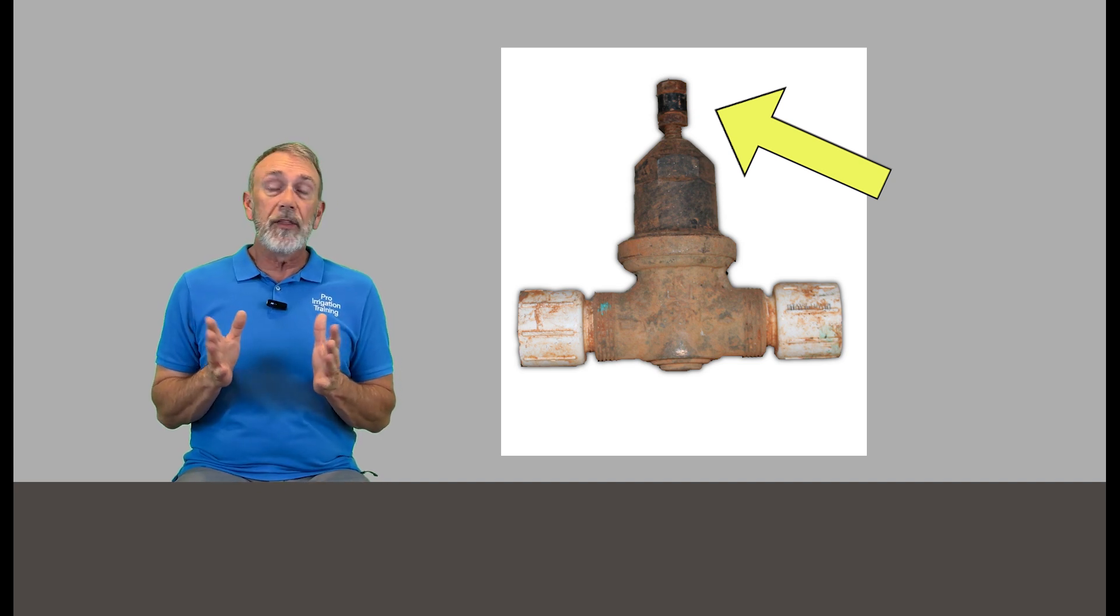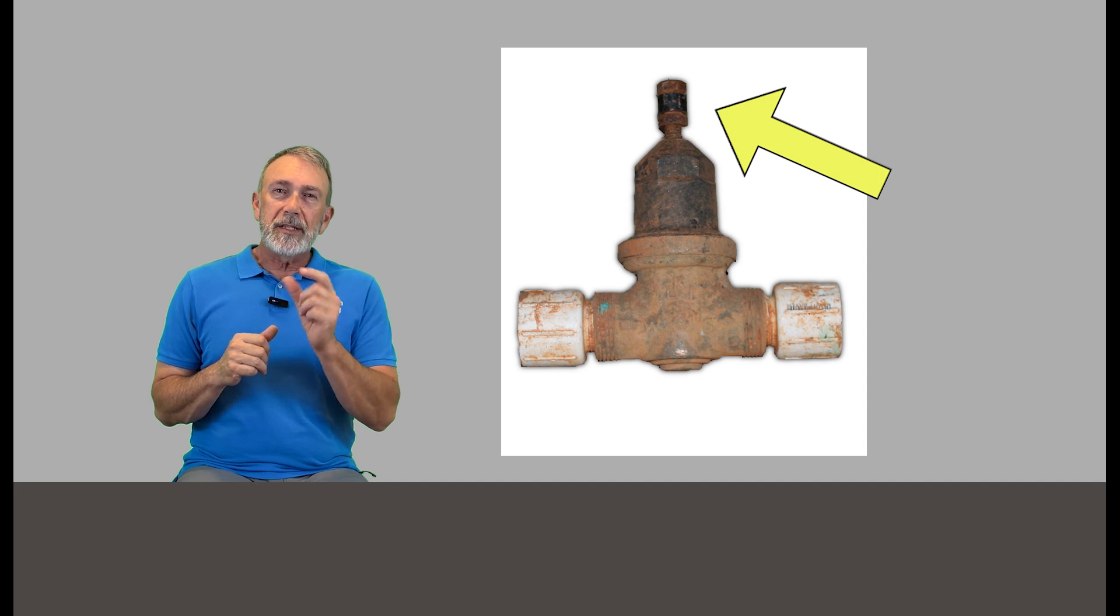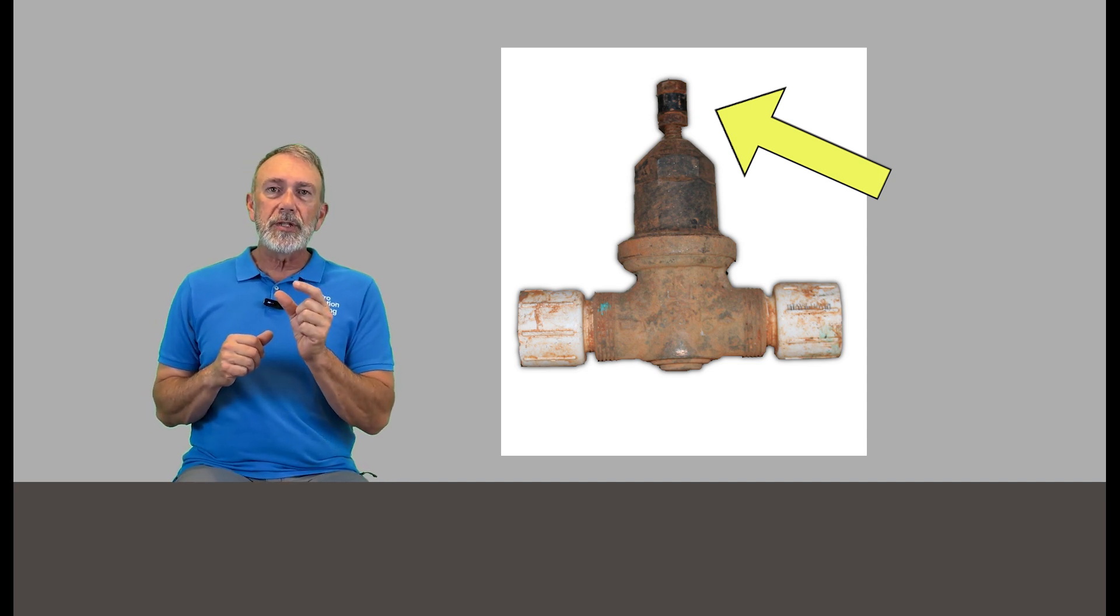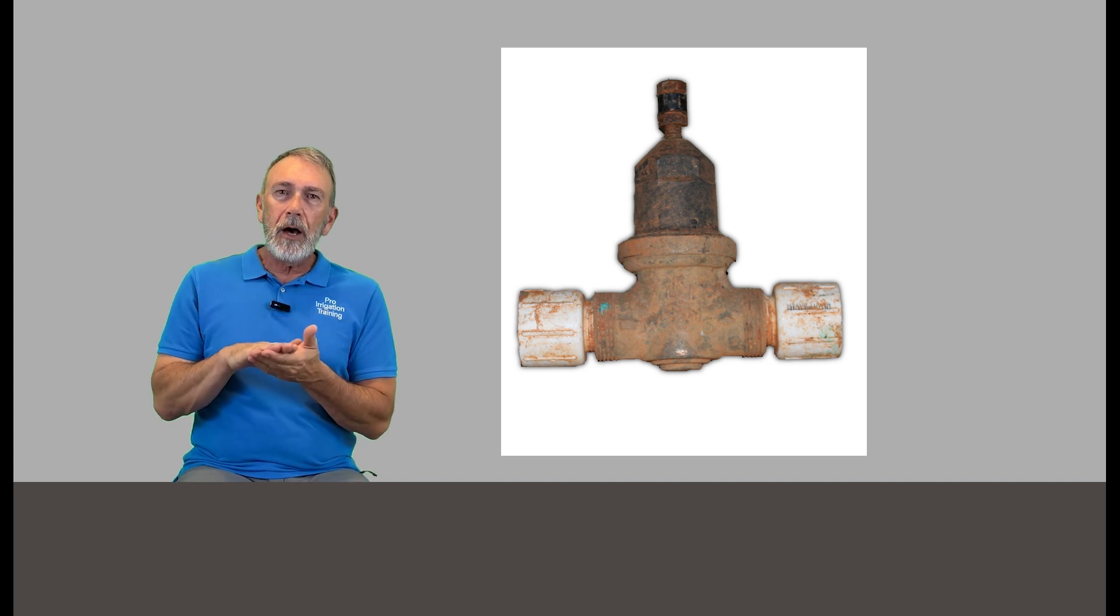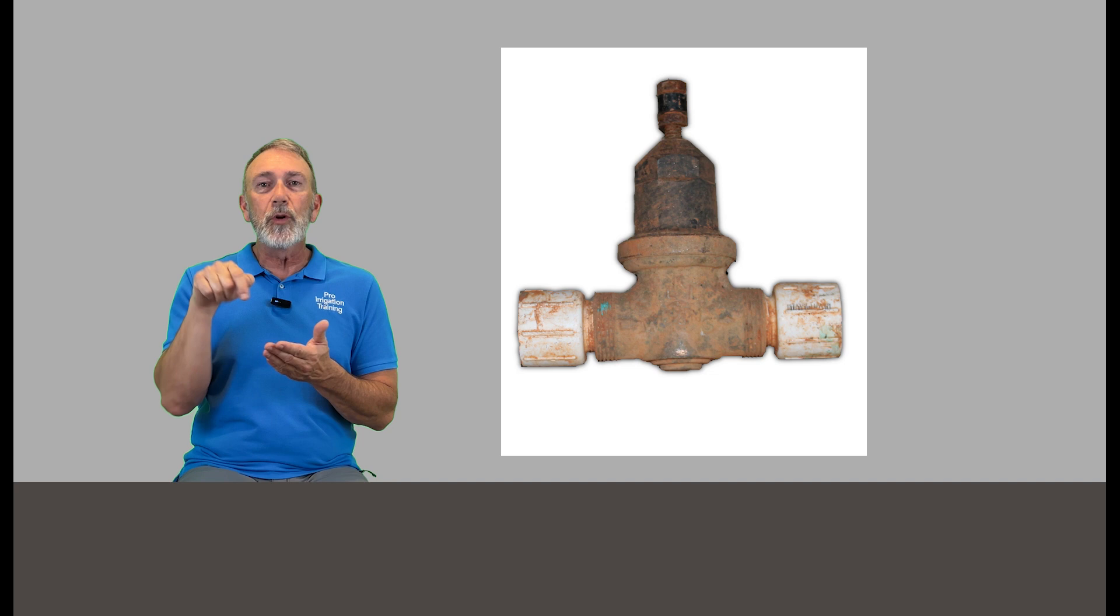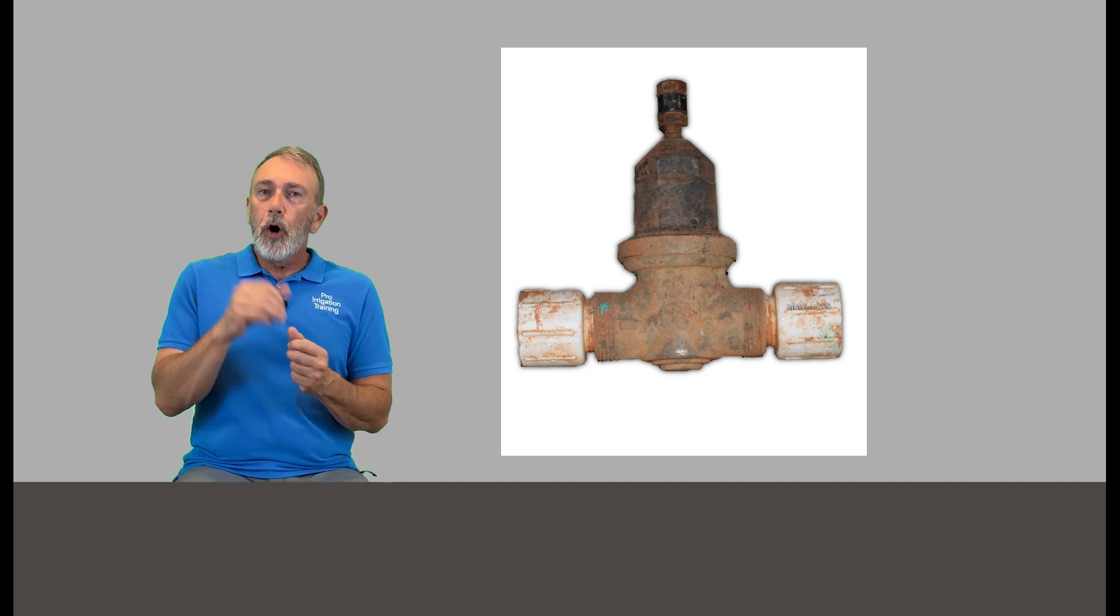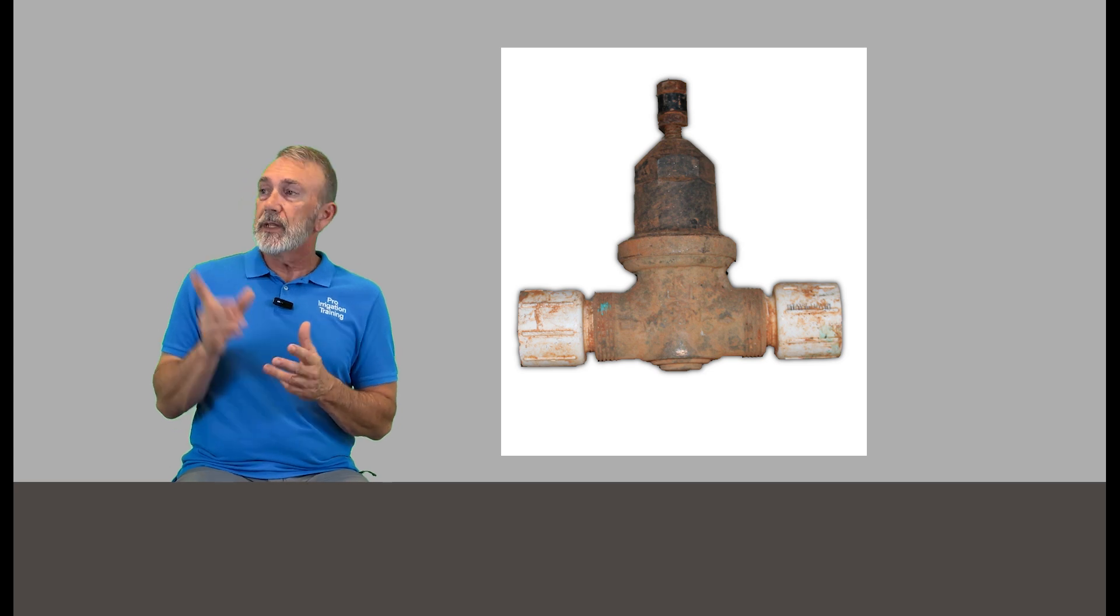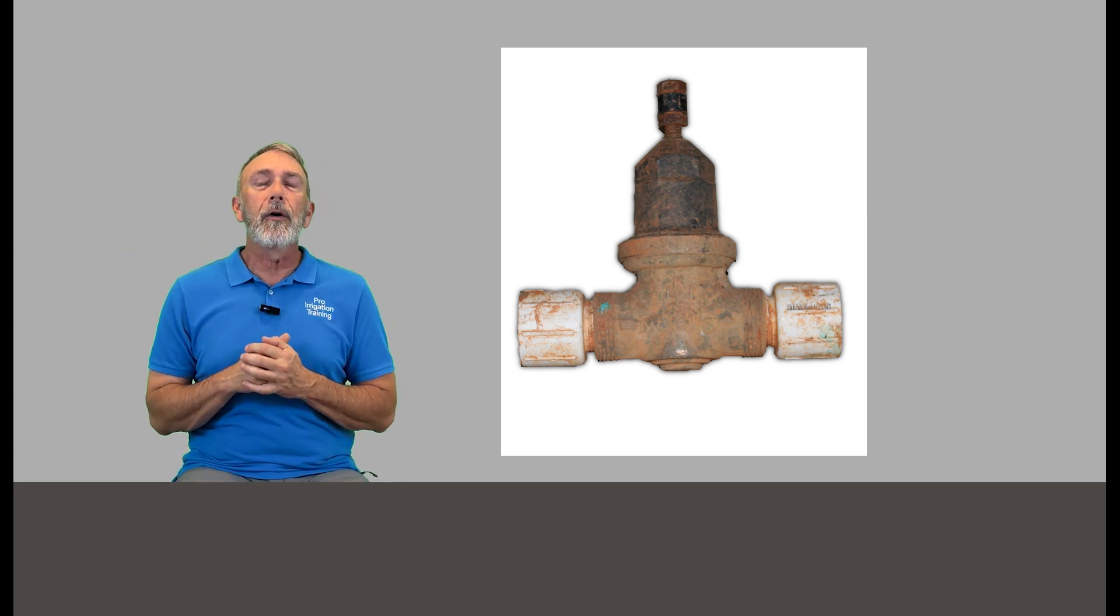On these pressure reducing valves, every one I've ever dealt with, the adjustment of it is kind of backwards. It's not righty-tighty, lefty-loosey. Whereas righty-tighty, you would think that that would shut it down and close down the pressure, but actually a clockwise righty movement actually opens it up. So it's just backwards. Open this pressure reducing valve all the way open. See if it affects the valve that we're watching or the zone that we're keeping our eye on here.